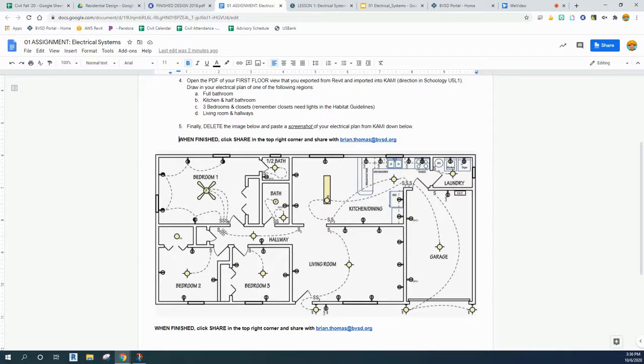But there's one thing that's kind of interesting here, and they are switching these outlets, which is really kind of an odd thing. Typically, you would not switch every single outlet. You may have one outlet that is switched, but the rest of them should remain hot or active at all times. So that is very atypical and something I would not recommend at all. So this one just has a single switch to the fan light and a single switch to the fan. That's SF, which would stand for fan. So those are different ways that you can annotate that.